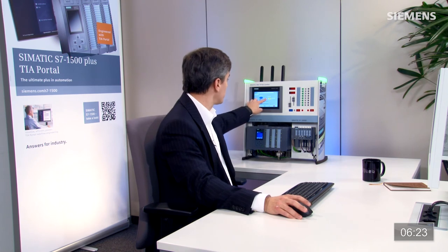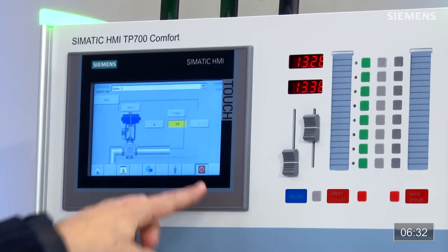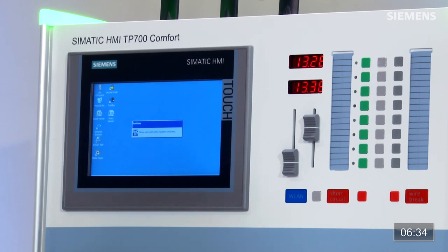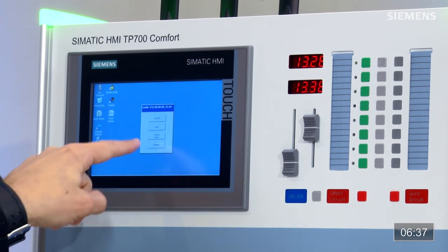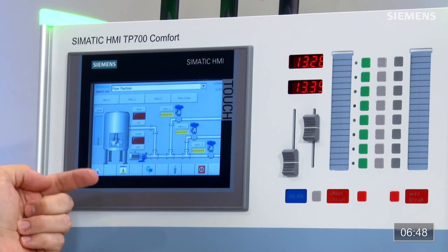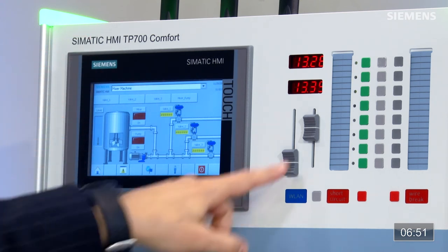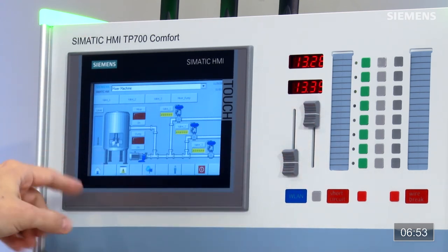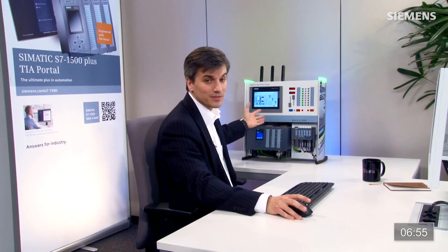Je conserve un contrôle total depuis le pupitre parce que j'ai une connexion existante. C'est au rétablissement de la connexion que cela prend effet. Je vais arrêter le Runtime, c'est le moyen le plus facile. Une fois que le Runtime est complètement arrêté, je le redémarre. Il essaye alors de se reconnecter à une CPU présentant une protection de niveau 4. Mais vous voyez tout de suite que ce champ de variables est hachuré : les pompes n'indiquent pas si elles sont en marche et le curseur est sans effet sur le niveau. Le système est totalement fonctionnel, mais le pupitre opérateur ne voit pas ce que voit le contrôleur.